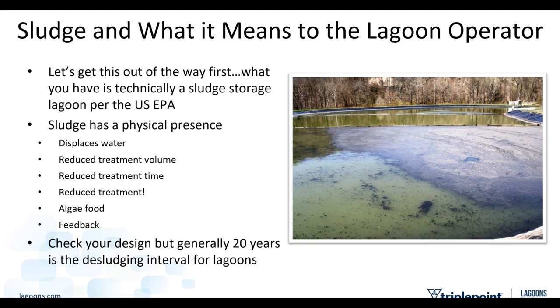And it's important to understand that what the EPA calls that thing out there is a sludge storage lagoon. It is not a wastewater treatment lagoon, according to the EPA. It's a sludge storage lagoon. The treatment has happened coincidentally, and we're doing the right things to set the stage to get the treatment we want. But we have to keep sludge in mind for a number of reasons. Right there on the screen, it's displacing water, reducing volume and treatment time. It feeds algae, and you have the potential for feedback.